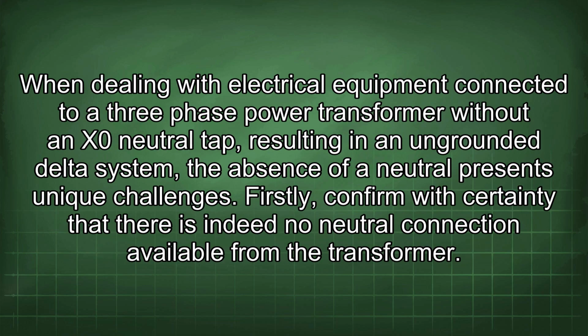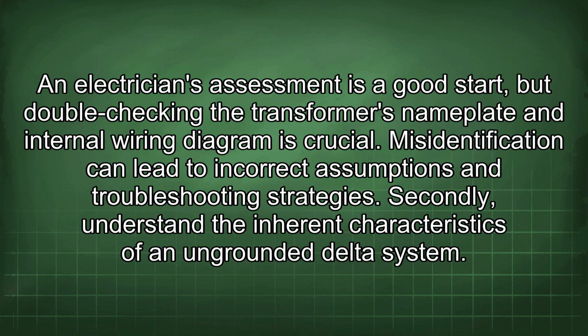When dealing with electrical equipment connected to a three-phase power transformer without an X0 neutral tap, resulting in an ungrounded delta system, the absence of a neutral presents unique challenges. Firstly, confirm with certainty that there is indeed no neutral connection available from the transformer. An electrician's assessment is a good start, but double-checking the transformer's nameplate and internal wiring diagram is crucial. Misidentification can lead to incorrect assumptions and troubleshooting strategies.